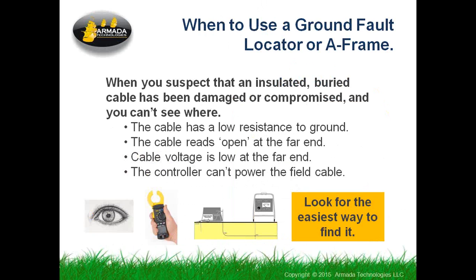To know when the cable has had some damage, you can use an electrical meter, very commonly used, to determine if there is a low resistance to ground from the insulated cable. And the cables we're talking about here are insulated copper cables, typically control wires for irrigation, power wires even for remote pumps, any number of insulated cables. And the problem that's occurred is that there is a compromise in the insulation that's caused a low resistance to ground. You can measure those with a meter and determine if that's really the case.